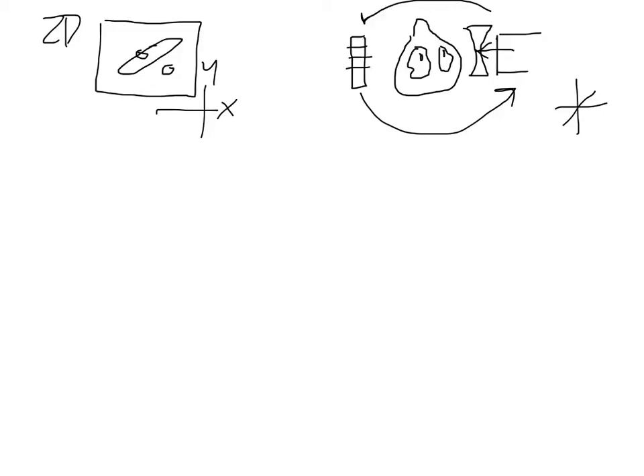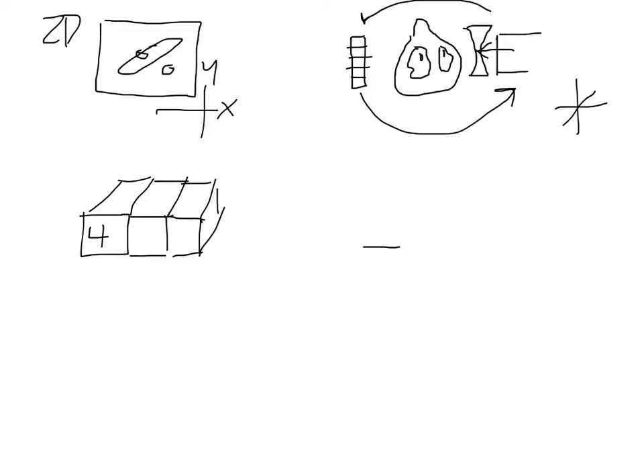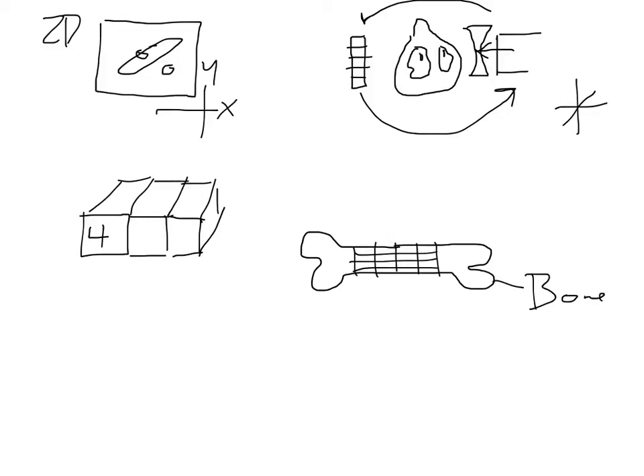On the receptor side, we have millions and millions of voxels. These voxels are like little image receptor banks — little three-dimensional receptors. Whenever an X-ray beam strikes one of those voxels, it records a number related to attenuation. For example, if we've got a bone made of millions and millions of voxels, it's going to record a high number.